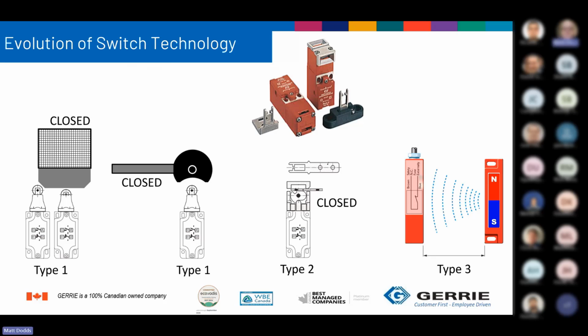So type 1 has a cam or hinge style means of actuation. In the rest or normal state, these contacts are normally closed when the actuator is not present and the guard is not closed. These must be used in a pair, where a second set of normally open contacts are held closed such that if the actuating cam goes out of alignment, they will spring open and stop the equipment. You see the example there where it opened up one switch and then the other one was forced open.